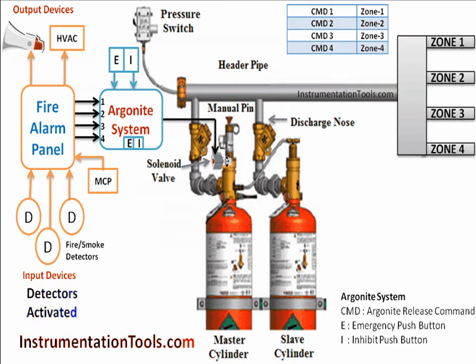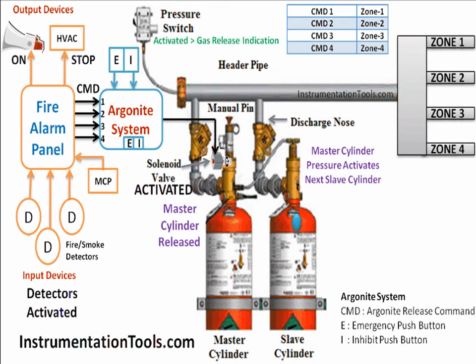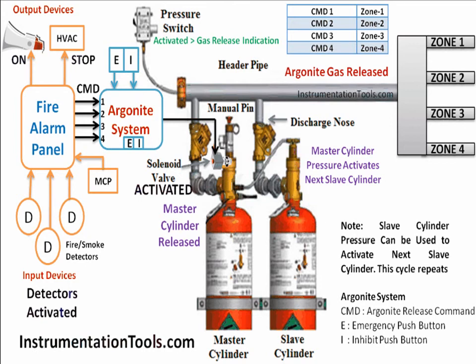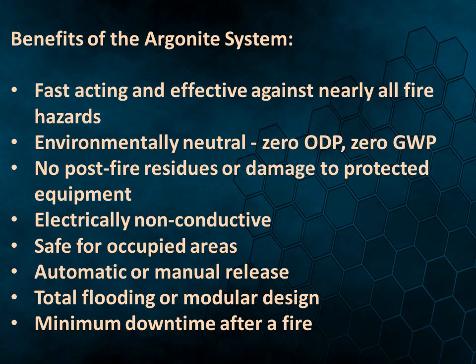A manual valve or release cutter pin is provided on all master cylinders. In case of automatic failure, we can use this manual valve to release the master cylinder, which then activates the remaining slave cylinders. Emergency push buttons are also installed near the Argonite System or respective zones, and are provided on the Argonite panel as shown in the animation. Pressure switches are installed in the main discharge line or specific zones, and Argonite gas release indication is taken from these pressure switches.